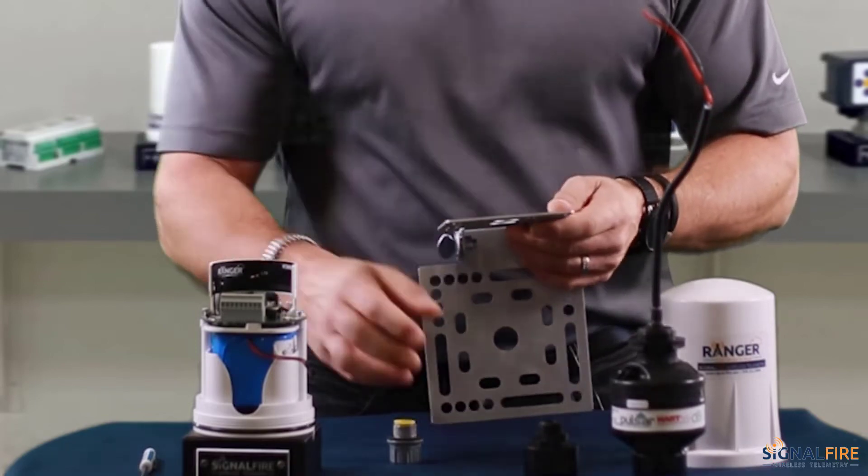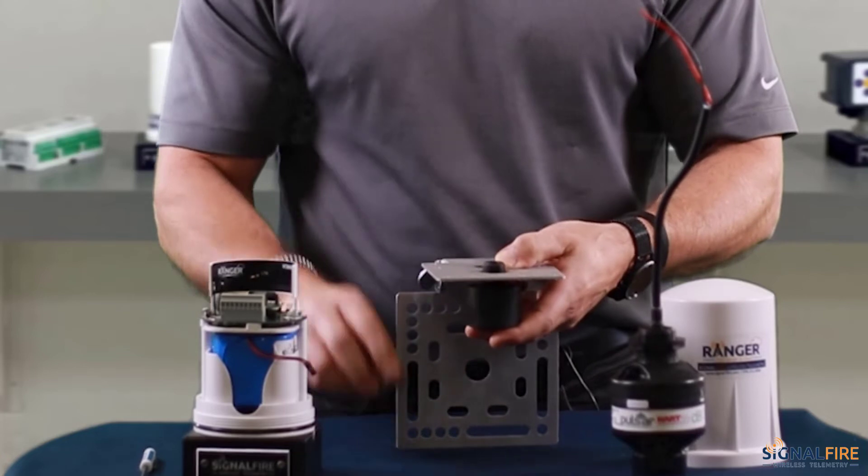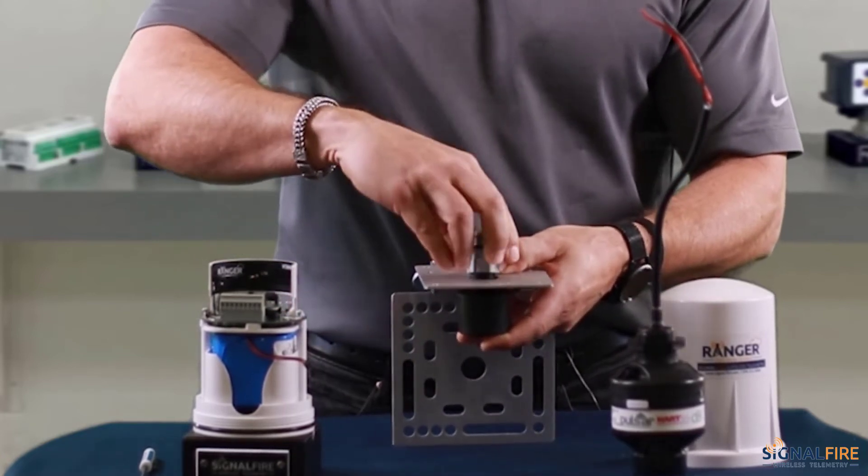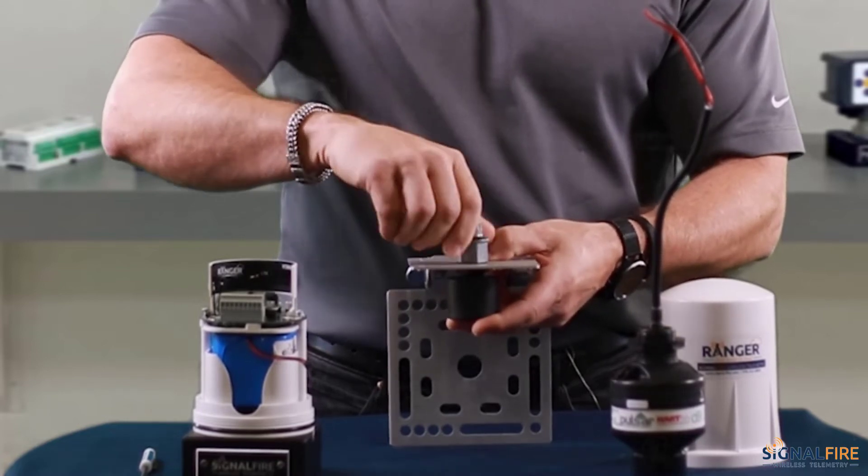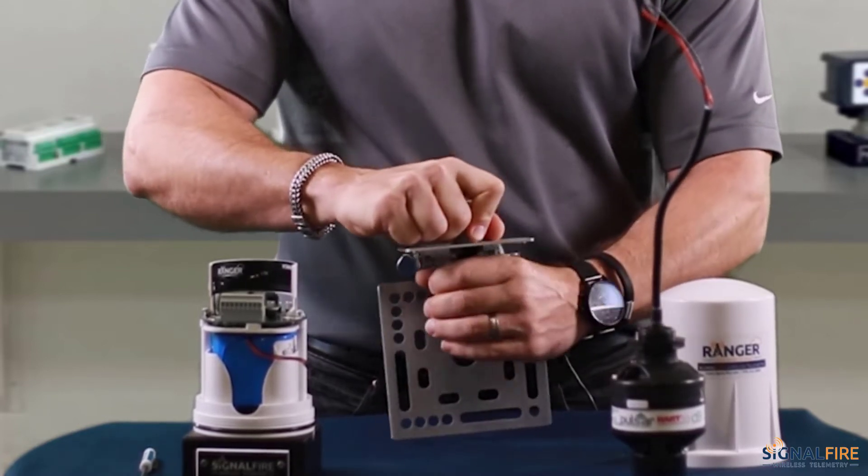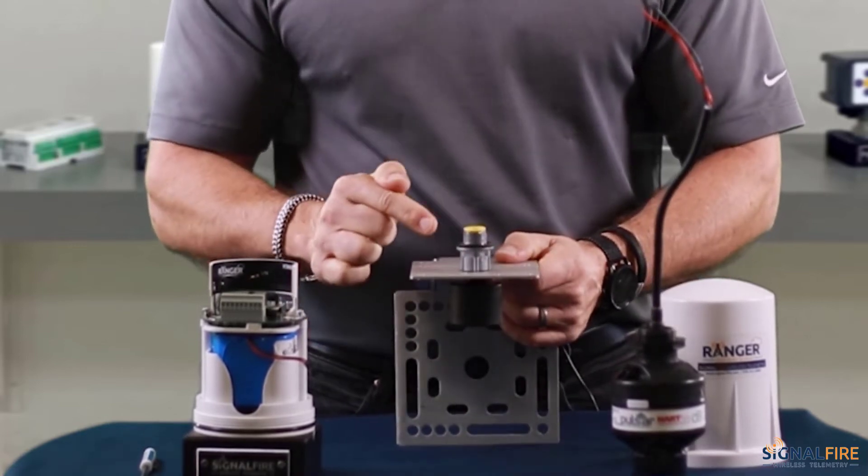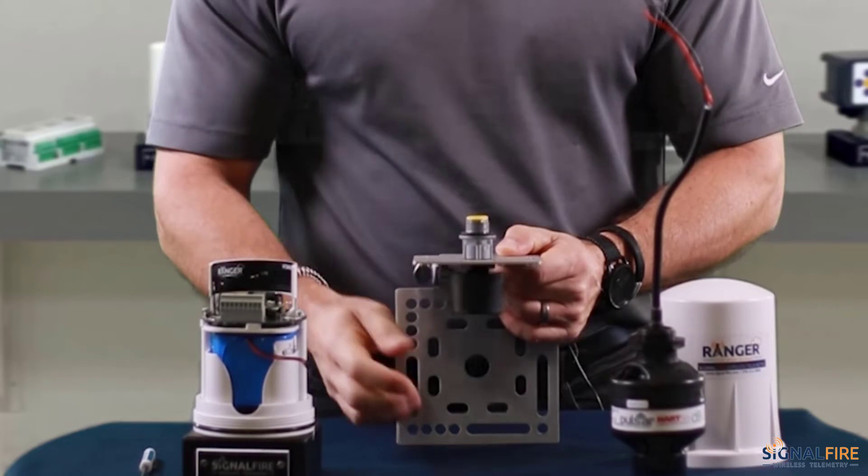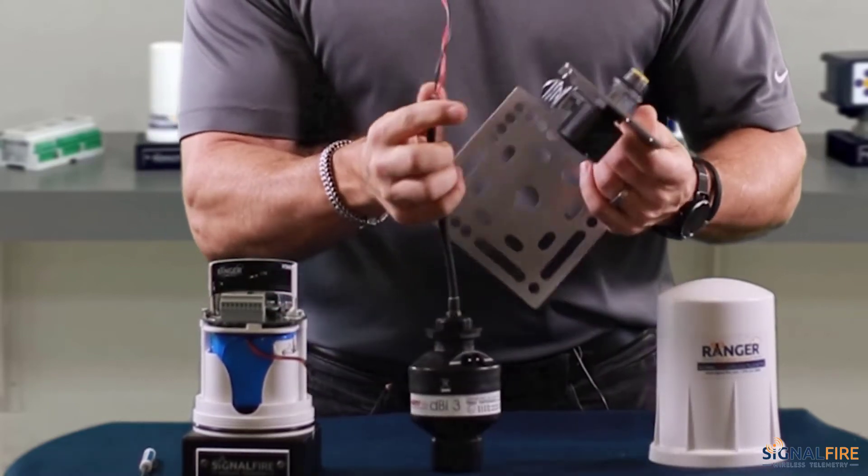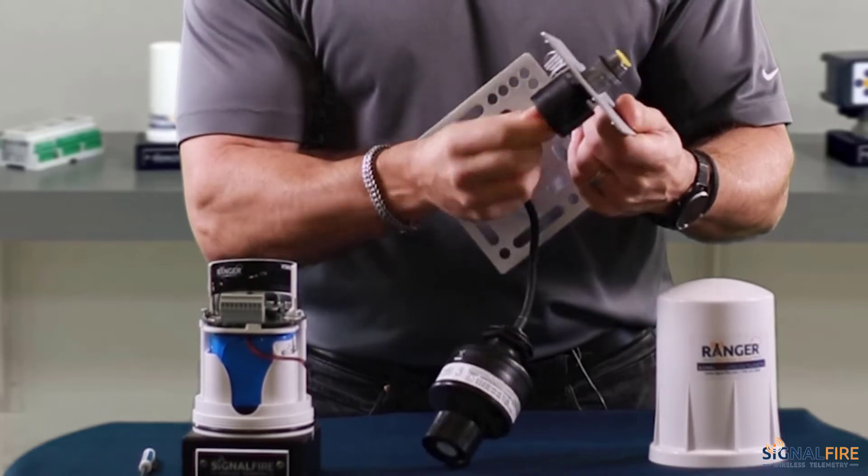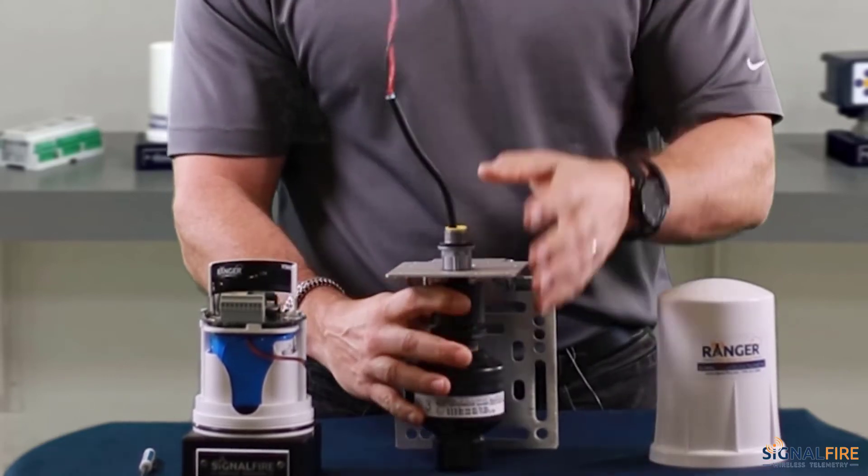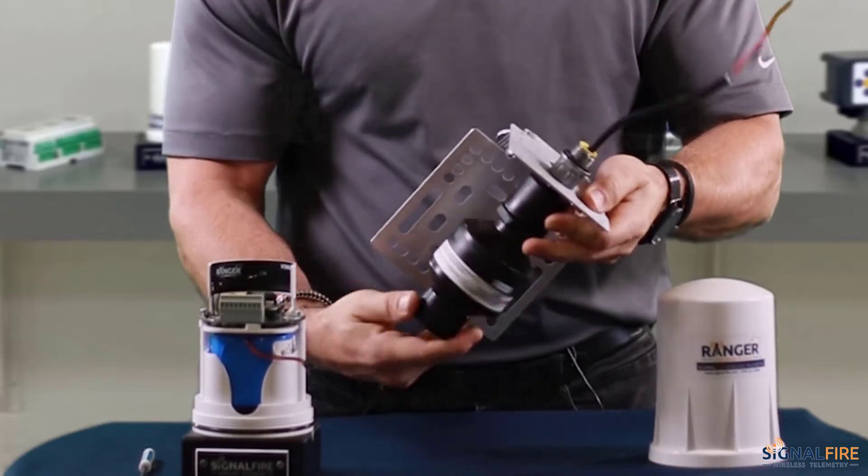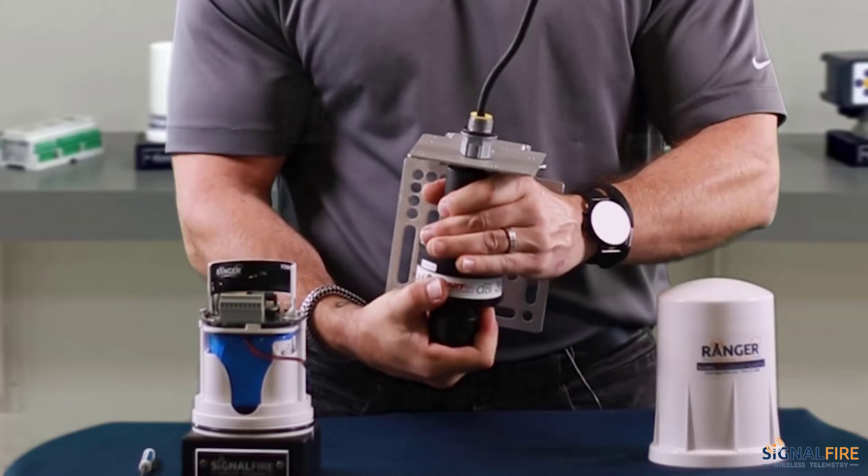Part one, let's couple the reducer with the cable gland. For the purpose of this exercise and this video, I will not be using Teflon tape on those threads, but highly recommend to do it. Secure the coupler with the cable gland. The next part is routing the cable through the reducer and the cable gland assembly, pull it through, and then tighten up the level sensor with the cable reducer.